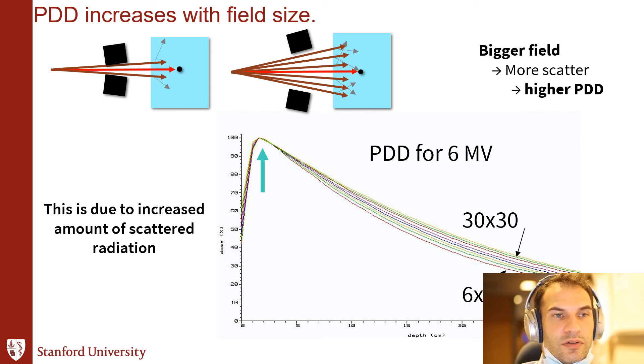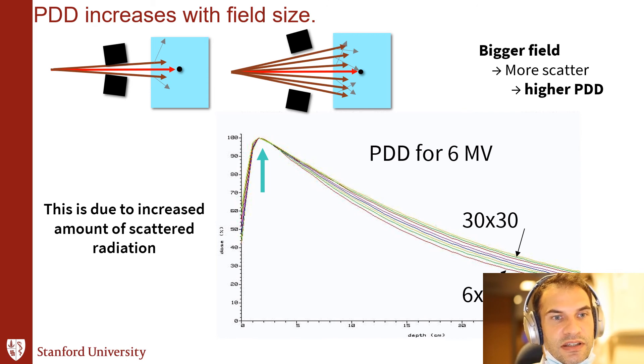PDD also increases with field size — more specifically, the slope gets more shallow. At deeper depths, the value of PDD at a given depth increases with increasing field size. It's simply because the bigger the field size, the more scattered radiation contributes, which raises the PDD curve.